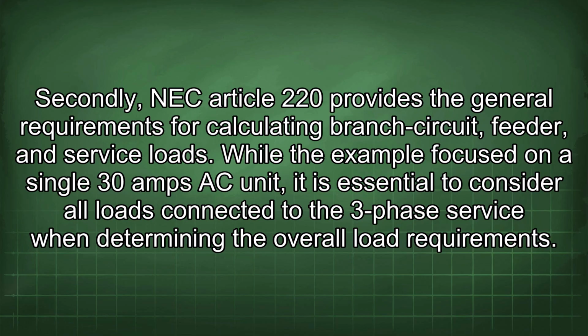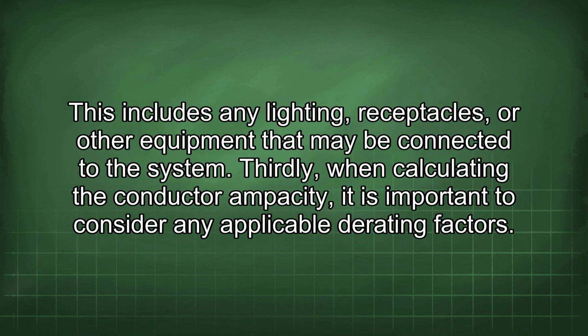Secondly, NEC Article 220 provides the general requirements for calculating branch circuit, feeder, and service loads. While the example focused on a single 30 amps AC unit, it is essential to consider all loads connected to the three-phase service when determining the overall load requirements. This includes any lighting, receptacles, or other equipment that may be connected to the system.